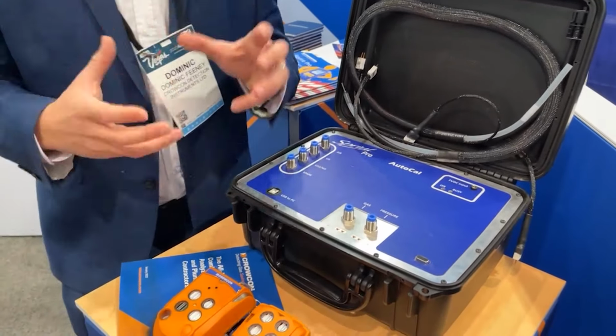With combustion analyzers, they have to be calibrated each year. The sensors degrade over time, for numerous reasons - sometimes how often they're used, sometimes how much CO is passed over them. But even if you never use it, over that year, just with the air, they do react. The electrolyte is consumed or dries out, and they lose sensitivity over time. So each year they have to be calibrated.